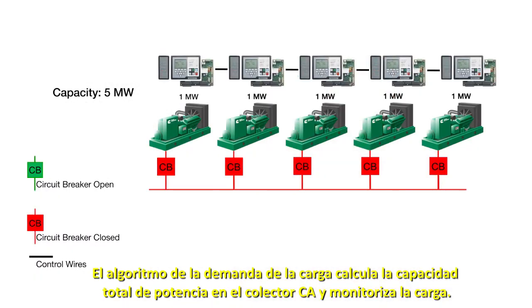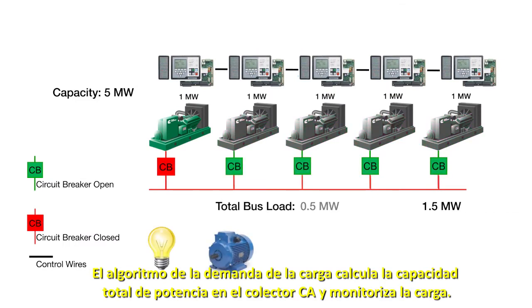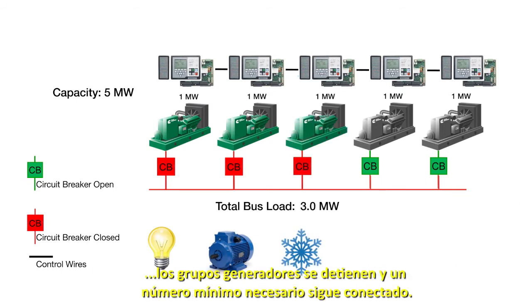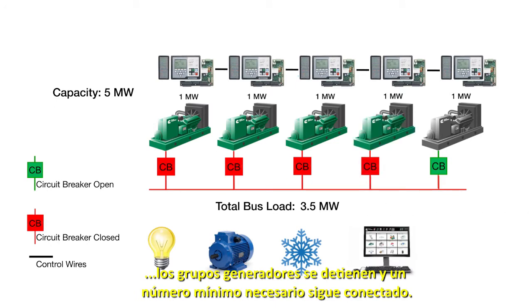Simply put, the load demand algorithm calculates the total power capacity on the AC bus and monitors the load. If the capacity is significantly higher than the connected loads, generator sets are stopped and the minimum number needed stay connected.